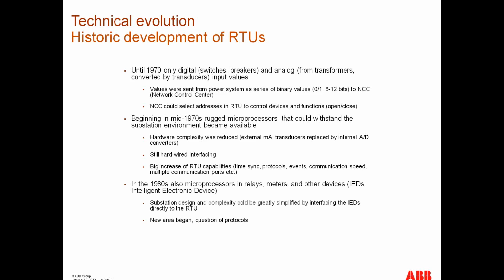The next step was in the 1980s, as microprocessors became common in relays and meters at the bay level, so different devices now had microprocessors. The abbreviation IED, Intelligent Electronic Device, came up for the first time around the 80s. This was the step where substation design and complexity could be greatly simplified by interfacing the IEDs directly to the RTU.